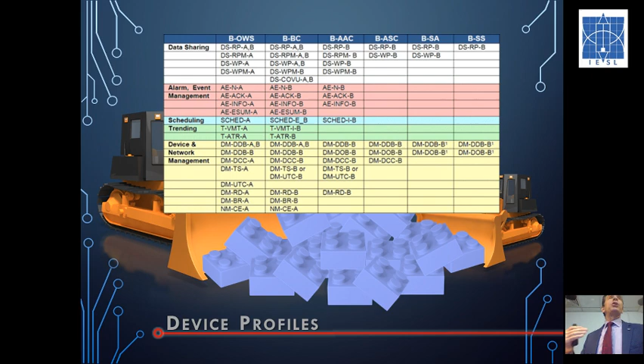So the BACnet testing laboratories come along, and because BACnet is an open protocol that's designed to the benefit of the end user, anybody can gain the BACnet protocol. Anybody can generate a BACnet device according to the profile that they want. They then submit it to BACnet. BACnet will test it. If it meets the minimum requirements of that profile, then they will work on their protocol implementation conformance statement, which goes back to the objects that we spoke about a little bit earlier, the properties, the data links and the sharing. Also, as part of the PICS statement, we need to be able to inform the services that are available, how we communicate, the rules on exchanging information. And that is done through the BACnet interoperability building blocks, which is the services.